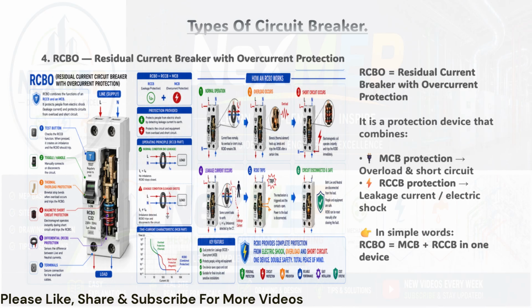The thermal element, a bimetal strip, detects slow overcurrents and bends to trip the device. The electromagnetic coil handles instantaneous short circuit faults. And the RCCB part uses a current transformer to monitor imbalance between the live and neutral, tripping the moment leakage is detected. RCBOs are increasingly the standard in modern distribution boards because they save space, reduce wiring complexity, and offer complete protection for each individual circuit. If you're designing a new DB panel today, RCBOs are often the smartest choice.